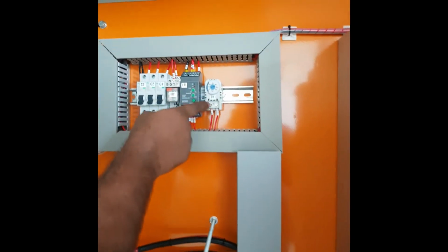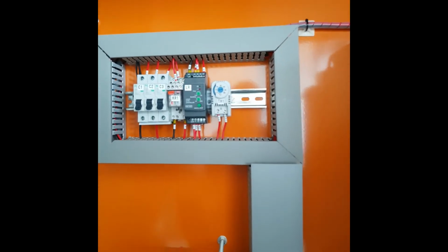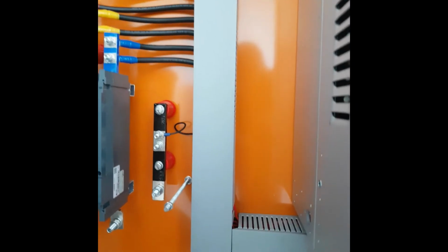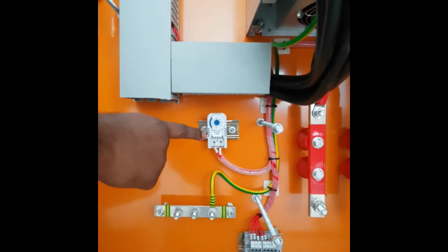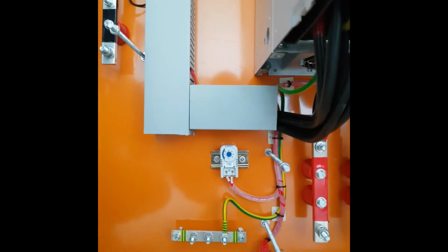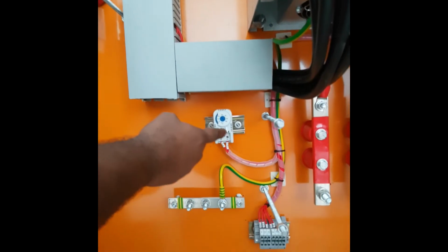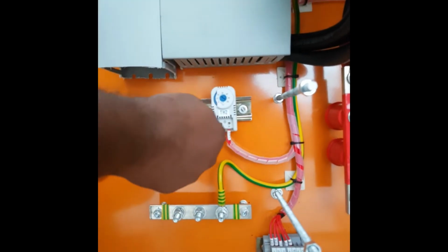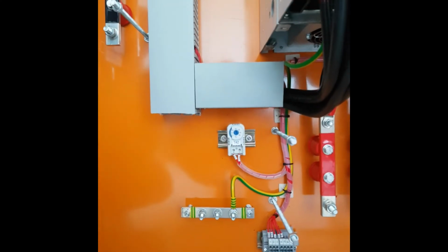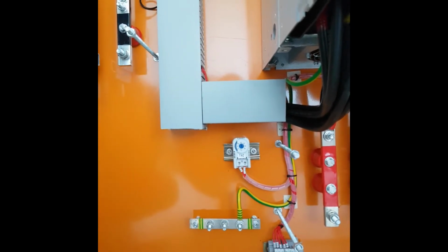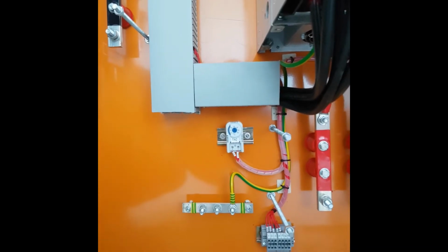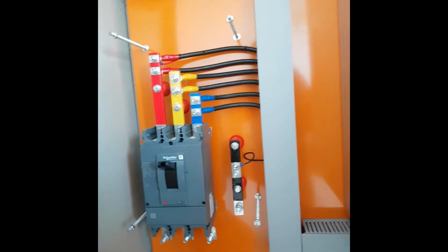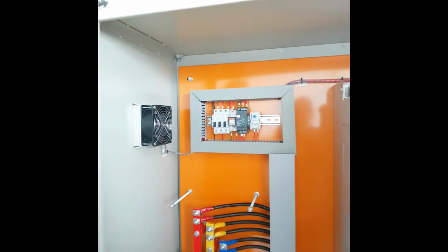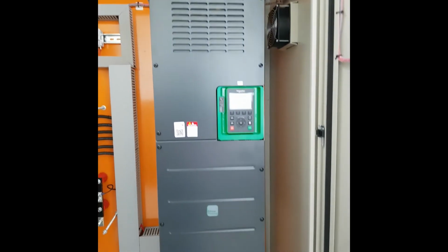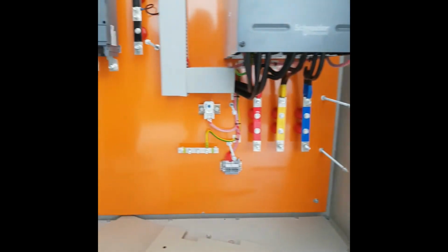You can see one thermostat here. This is TH1, thermostat 1, and this is thermostat 2. Each thermostat controls one fan. So you can set and monitor the inside panel temperature. Once this temperature rises above your setting temperature, the fan will start automatically and circulate the air from outside. It will remove the inside hot air and take fresh air from outside through this louver. You can see 2 exhaust fans installed on the top side and 2 air louvers installed on the bottom side.